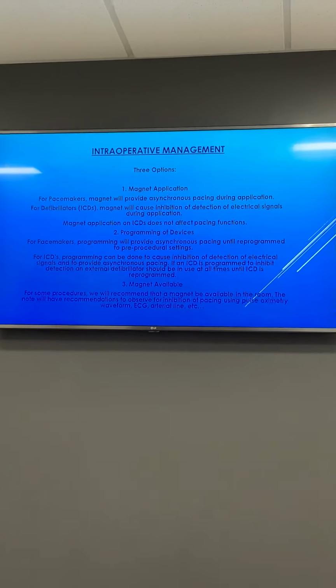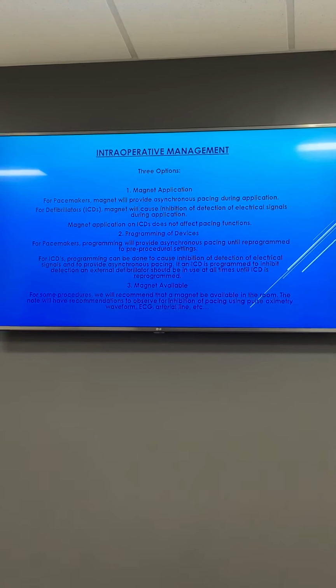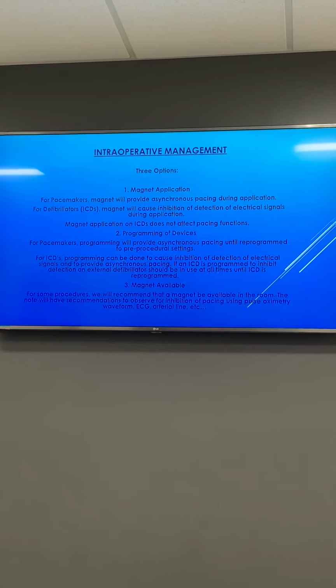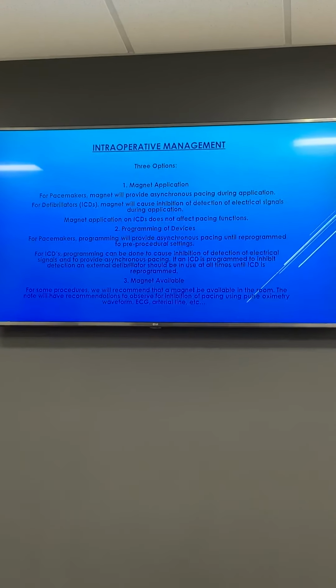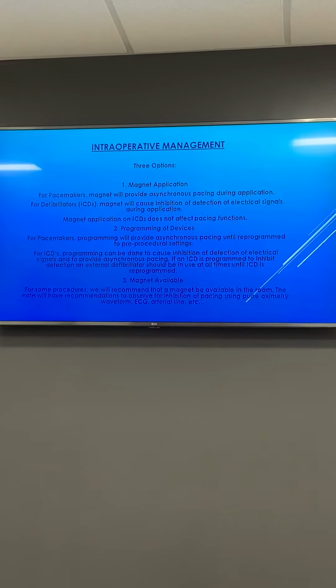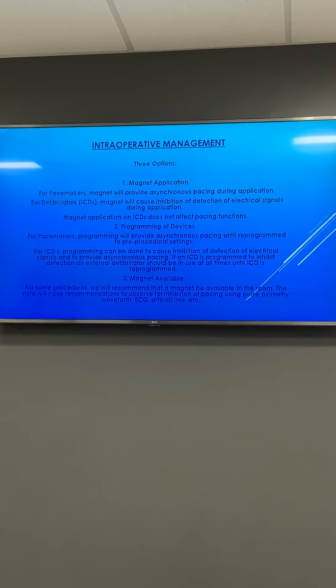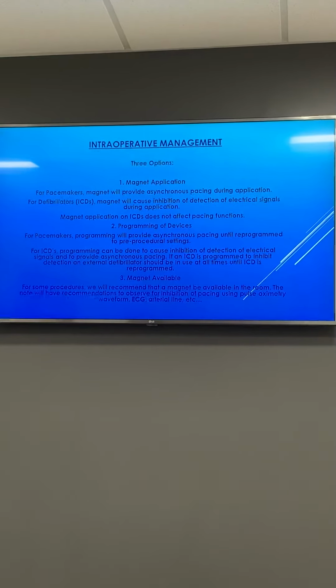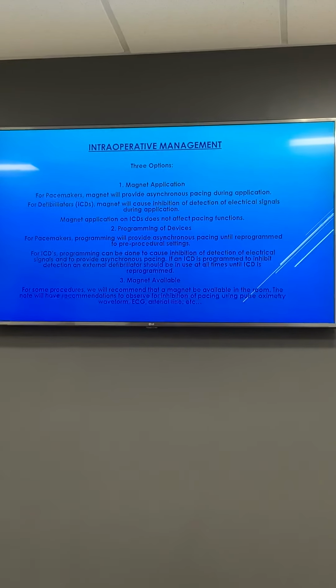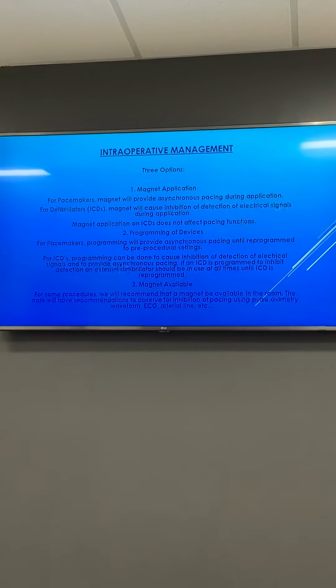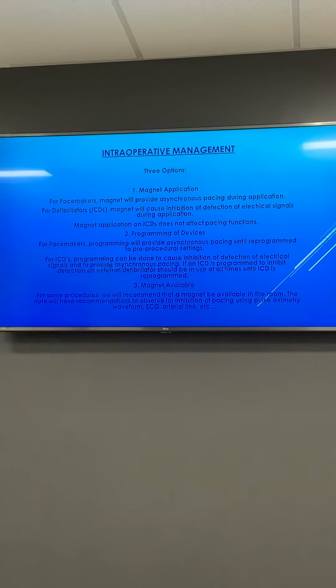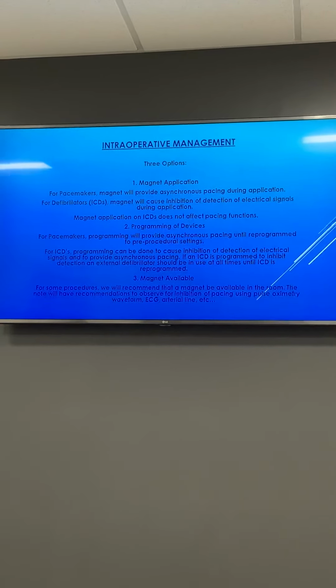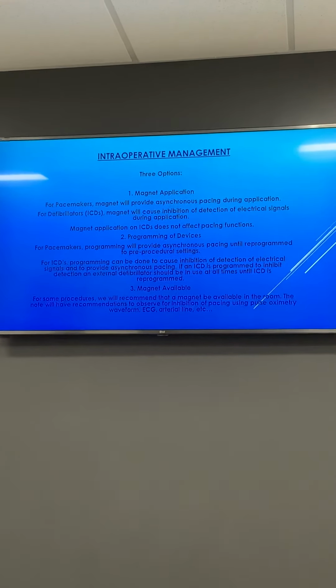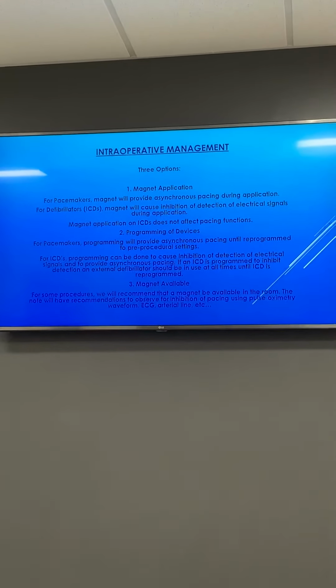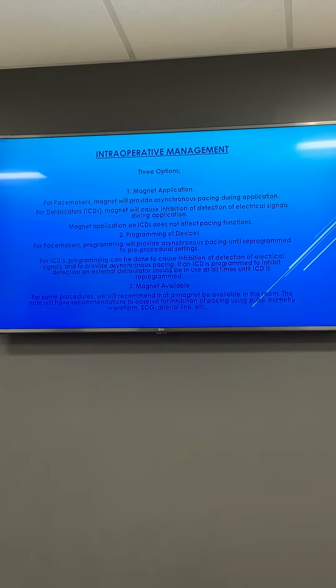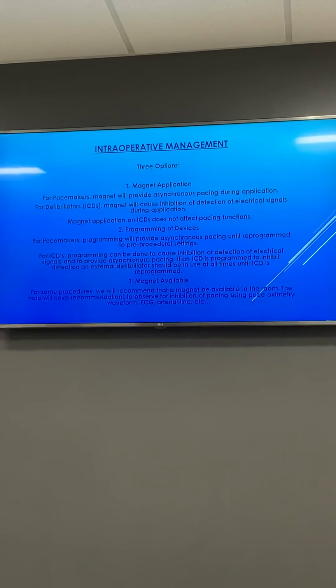For defibrillators, the magnet will make the device blind to any electrical activity, because the defibrillator is looking for electrical activity that it thinks is too fast to get ready to shock. So when you put a magnet over it, it's gonna say, okay, I don't need to pay attention because of electric cautery. I think they're better now, but in one of the OR rooms here, just plugging in something in the room would make the defibrillator pick up noise. So it just makes it not see any of the noise and makes it blind, so that way it won't defibrillate. The trick with that is you have to keep the magnet on top of it.